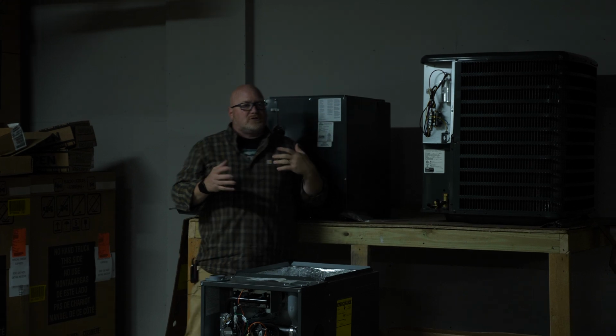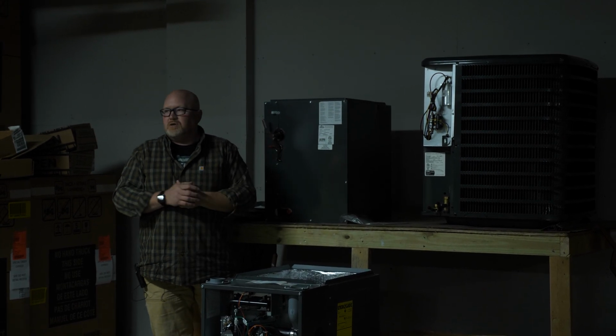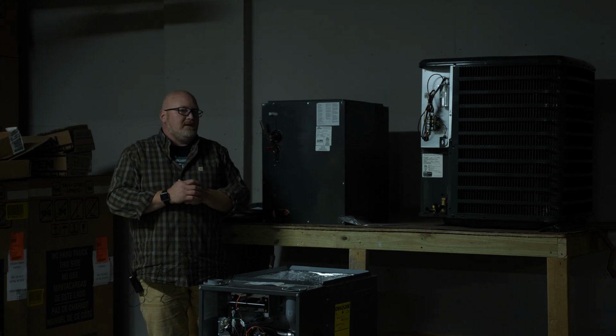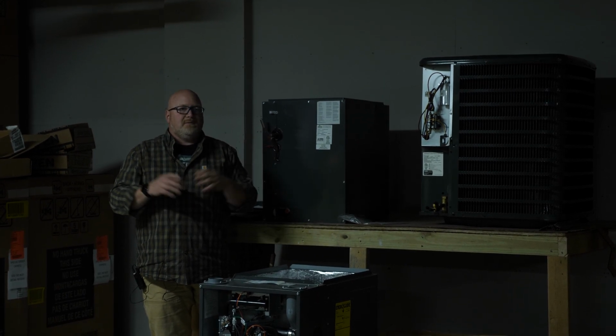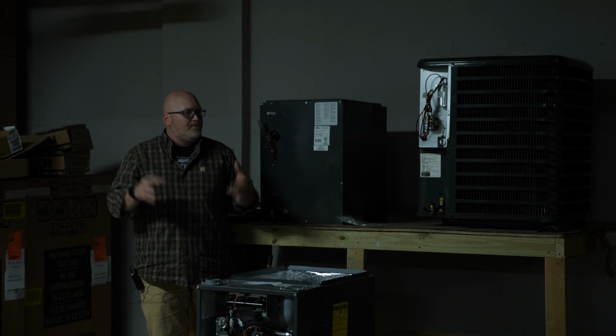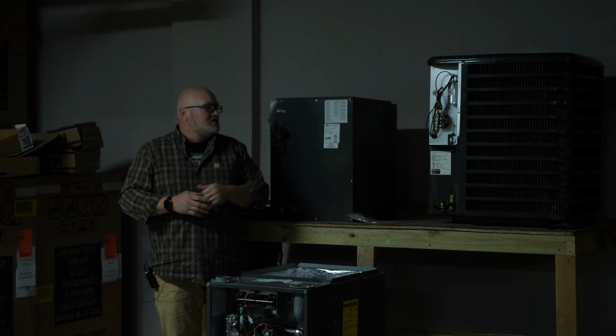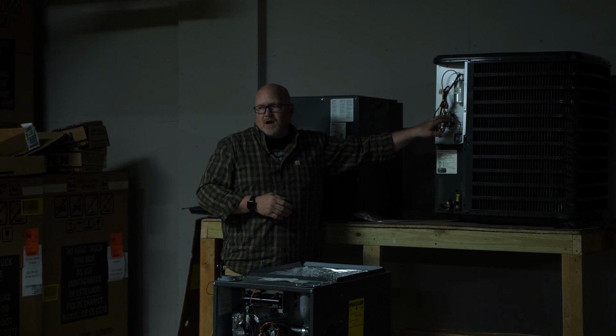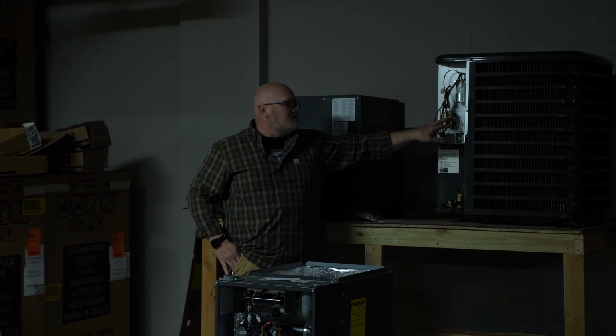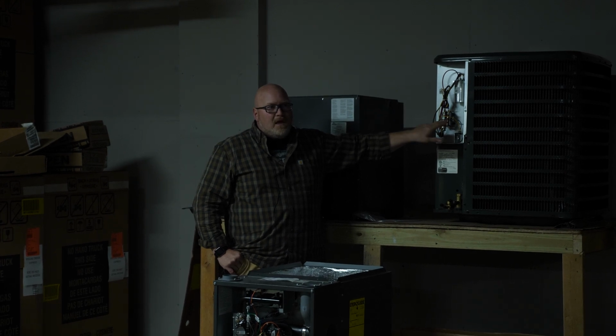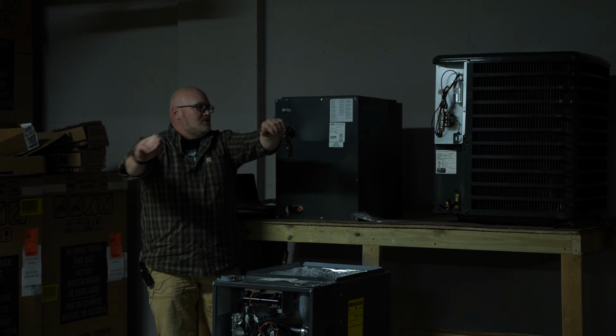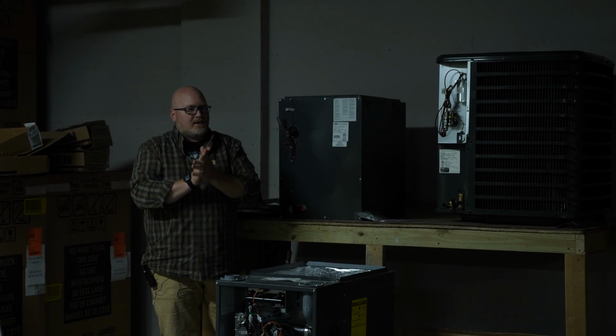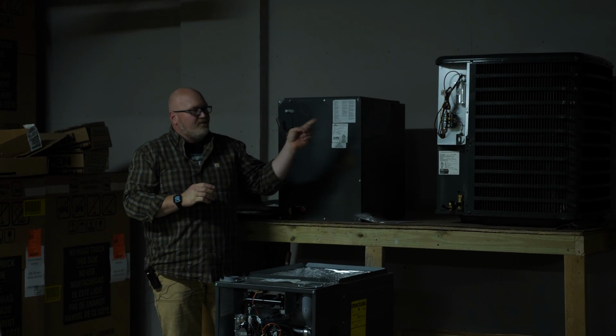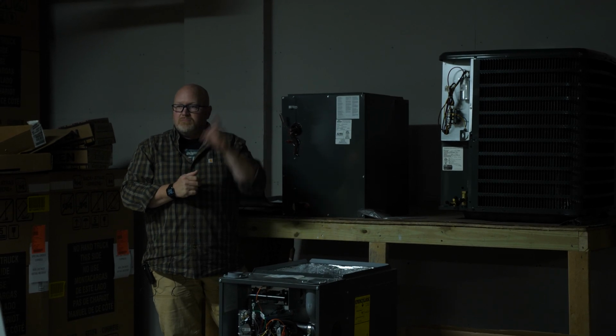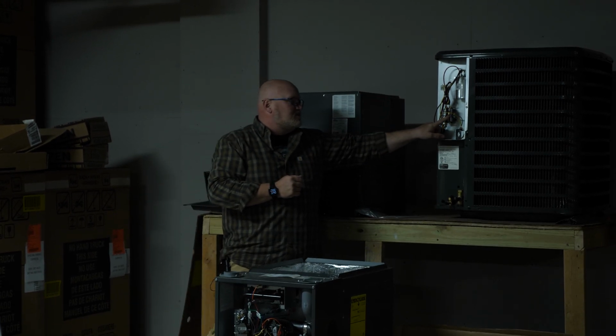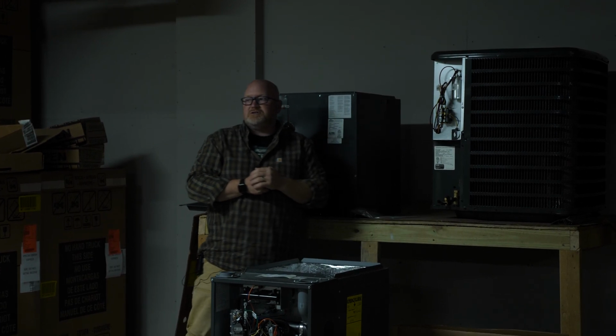Now, when we talk about serviceable issues or problems when your air conditioning goes down, realistically, probably 90% of that is going to be an electrical component. And it's an electrical component that is built to be replaced. So you walk outside, you got your air conditioning on, but you're not getting any cool air coming out, and you hear this chattering going on, that means that you need a new contactor. It means that your voltage is not holding to suck in that contactor to put line voltage on that compressor condenser. So number one is your electrical contactor. Easy, simple replacement to do.